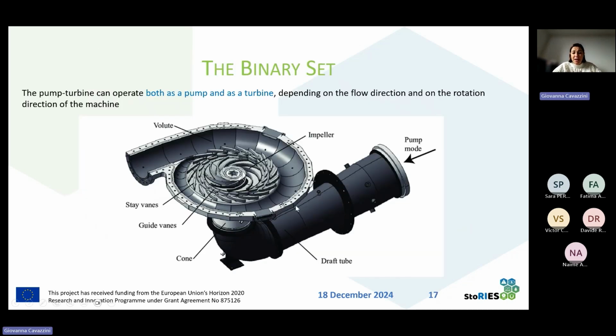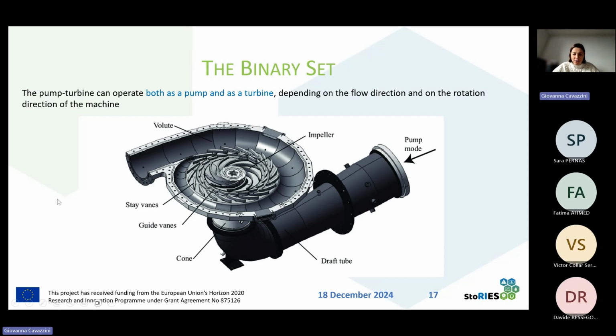Here you can see a detail of the pump turbine. Its operation is simple: depending on the flow direction and the rotation direction of the machine, it can work as a pump or as a turbine. In pumping mode, the water flow enters from the right and is discharged from the left, from the so-called spiral case. In turbine mode, the water enters in this direction, the runner rotates in the opposite direction, and the water is discharged from this pipe.